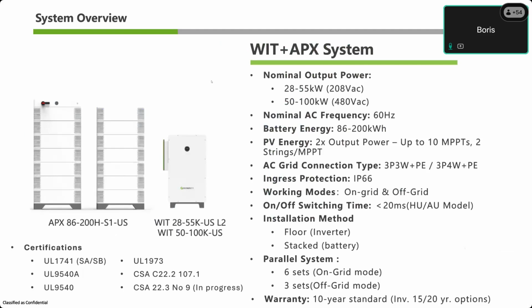We have those inputs directly on the inverter, on the side of the inverter. Can be Delta or Y connected, and is good for indoor or outdoor use. The only request, and I'll show this on the next slide, is if it's outdoor, we request an awning over the inverters, not so much for water, but more for solar loading.